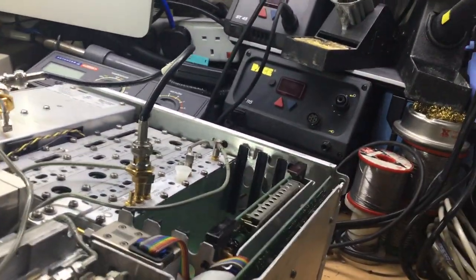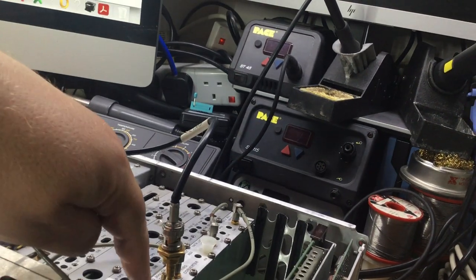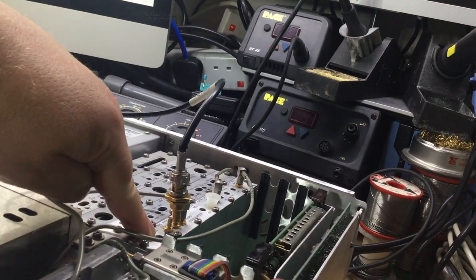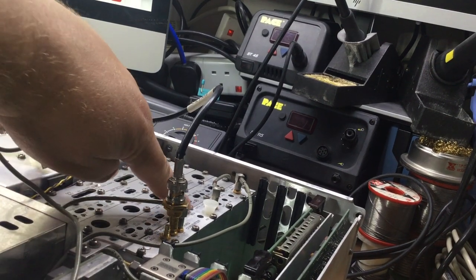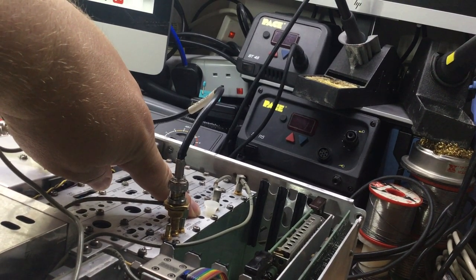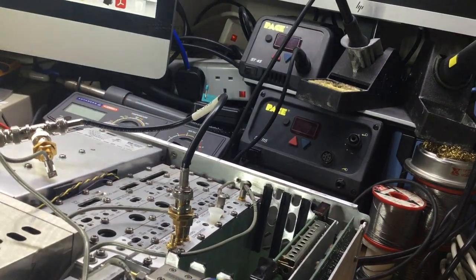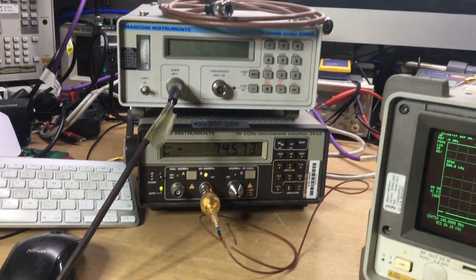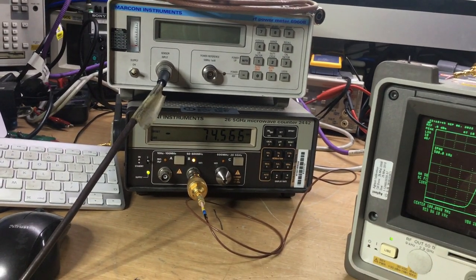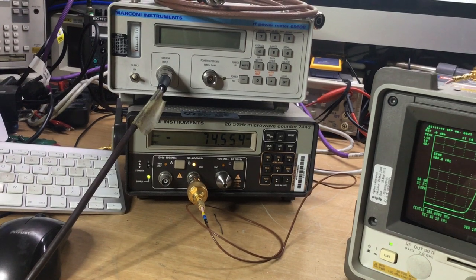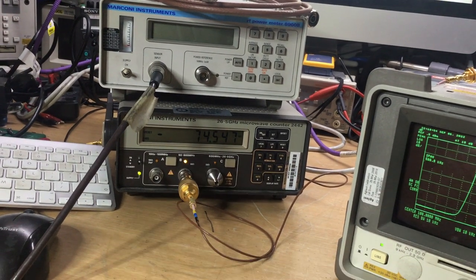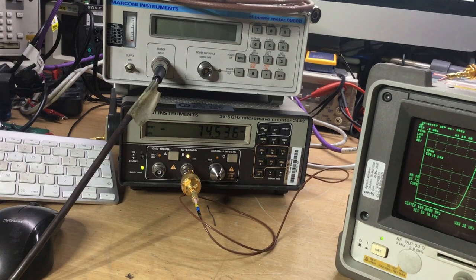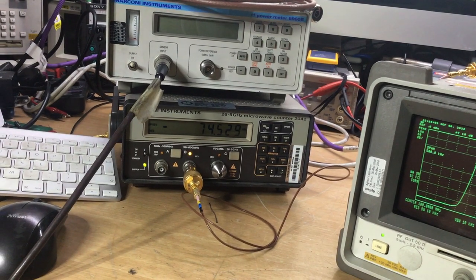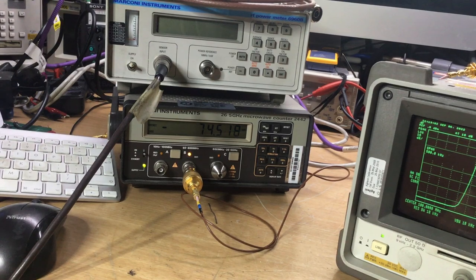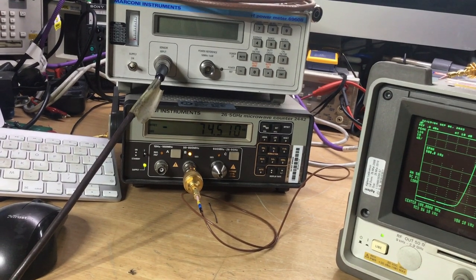So we've got two potentiometers: the 600 megahertz coarse frequency adjust there, and that's the level adjust for the calibrator, the 300 megahertz output. So we'll have a look at that next, see whether we can adjust it. It might be that I just have to twiddle the 10 meg oscillator again on the other side of the instrument, where we were looking at earlier, to get that frequency down if it's too far off. So there's a few little things that we can tinker with here, but once I get that frequency correct, then I think we'll be okay.